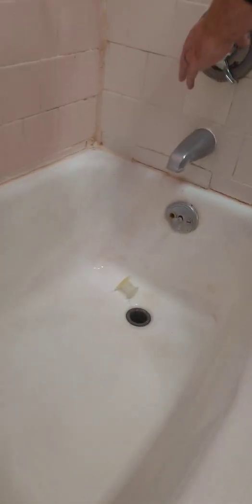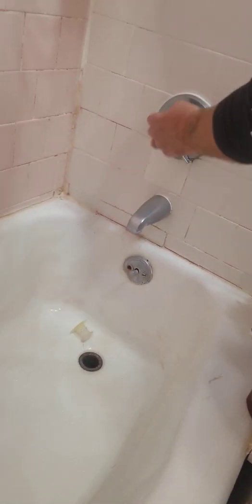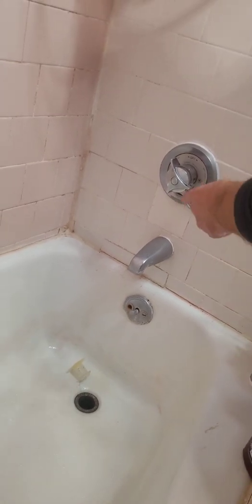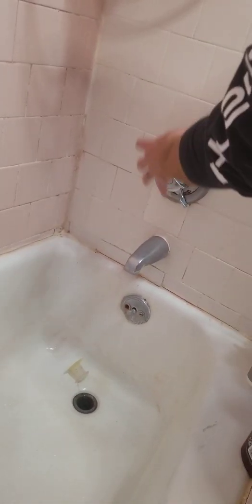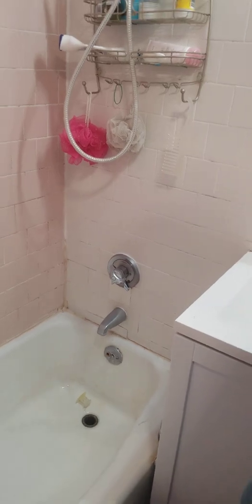And then what we do have is fine sink, but I do see that we have a dripping tubby here. So this valve, I'm going to pull this valve out and we're going to rebuild the valve. If I can't rebuild it, I'll just replace it altogether. Not the entire housing, I just need the Symmons valve. And we'll replace that. Most of the time I can just back it off and rebuild it. But we'll see what happens. We'll put this on our list as we got to do this.